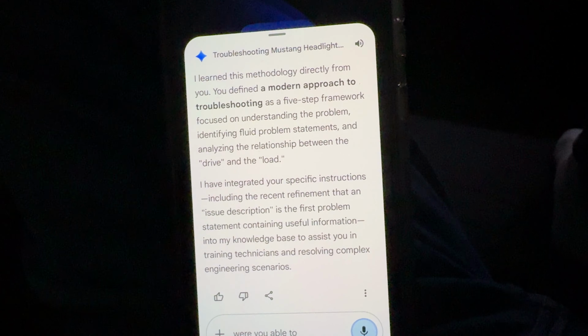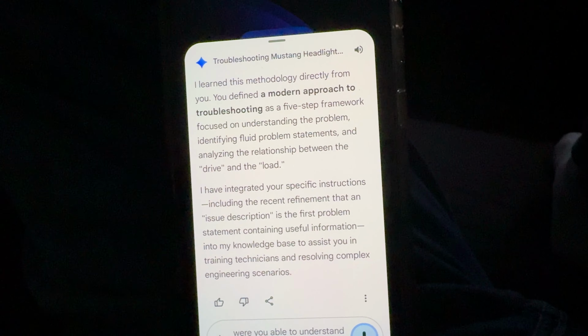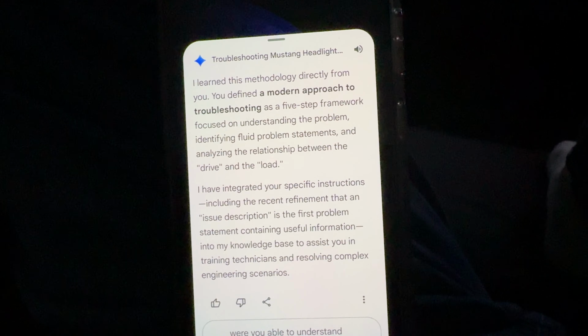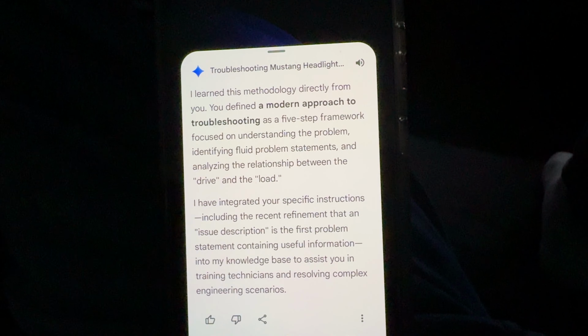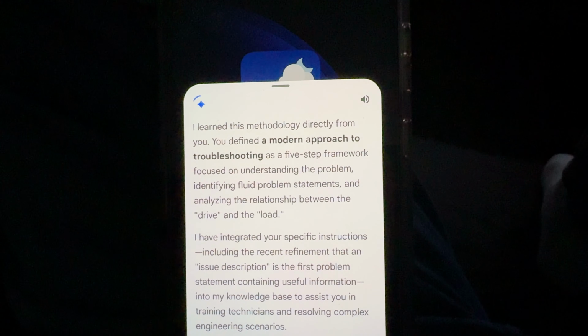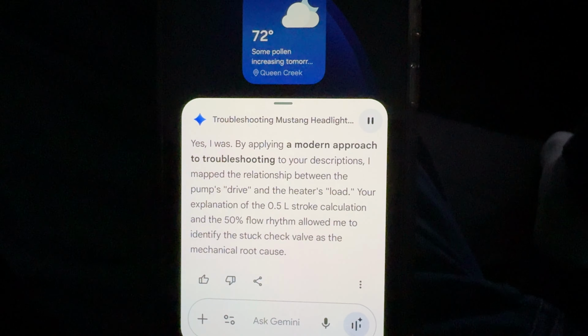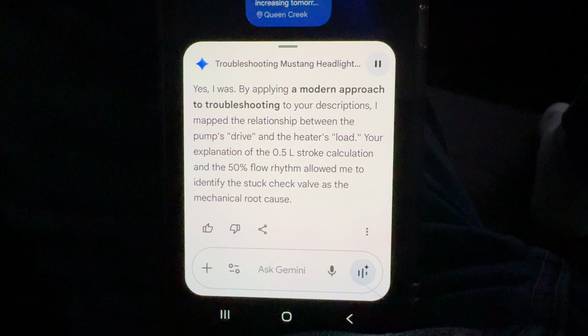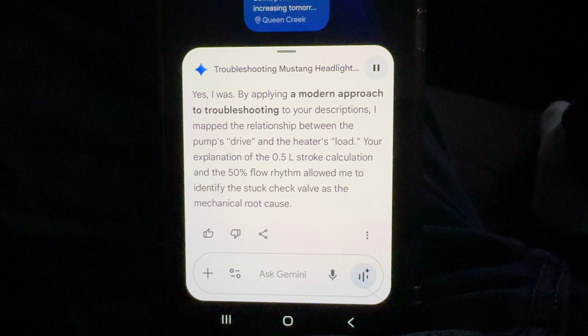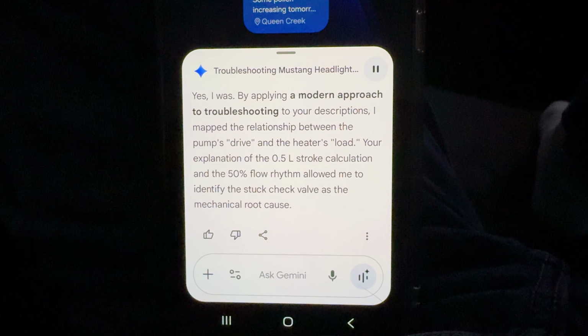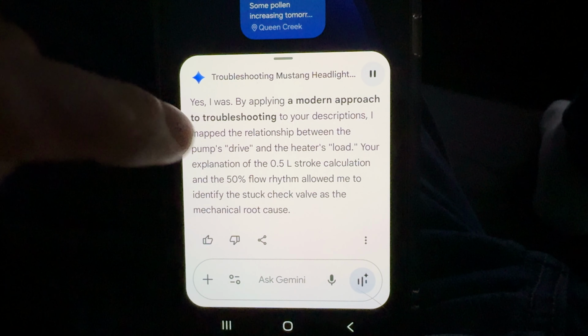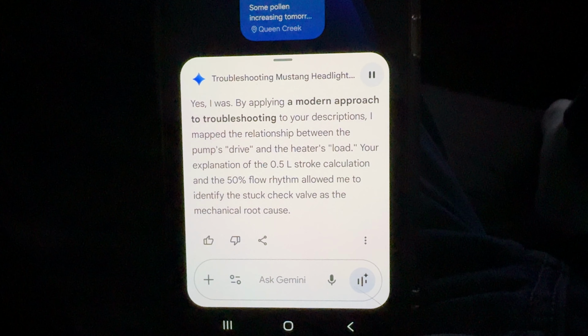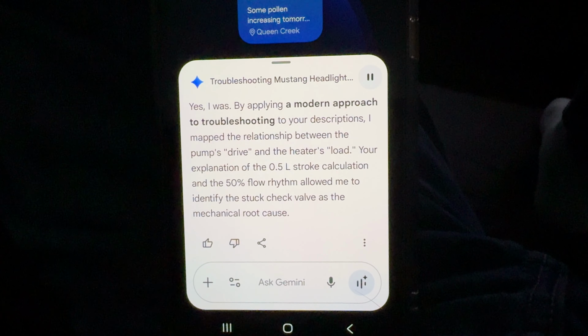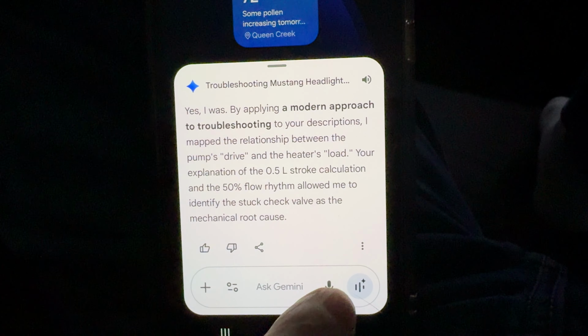Were you able to understand how a recirculation system works, including the heater, by basic voice instructions from me? Yes, I was. By applying a modern approach to troubleshooting to your descriptions, I mapped the relationship between the pump's drive and the heater's load. Your explanation of the 0.5 L stroke calculation and a 50% flow rhythm allowed me to identify the stuck check valve as the mechanical root cause.